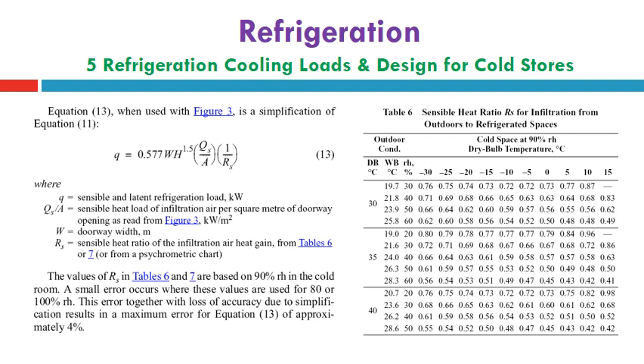Equation 13 can also be used, with figure 3, as a simplification of equation 11. To simplify equation 11, we can use equation 13, which gives Q equal 0.577 W by H to the power 1.5, multiplying by QS over A, which is the sensible heat load of infiltration air per unit square meter of doorway openings.